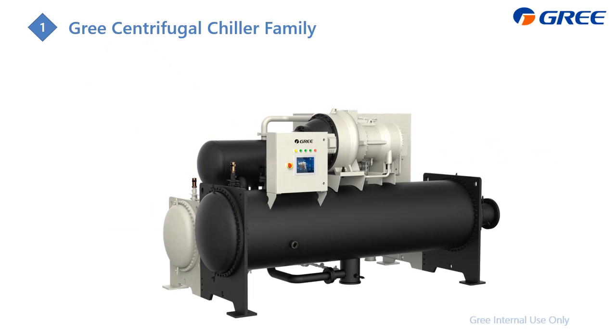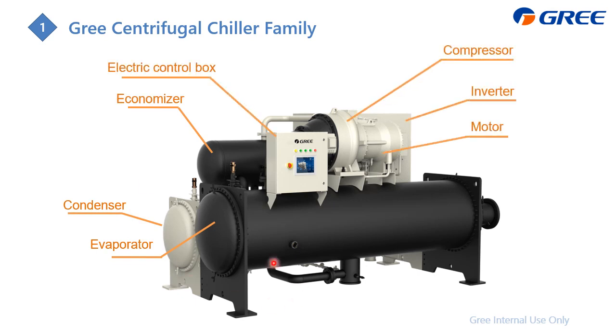This is the front view of the Gree centrifugal chiller. Let's recognize the components first. And this one, the black one, the black cylinder, you can also find it. It is the evaporator because it is doing cooling, so the surface always has insulation. And this one, condenser. No need to put insulation on the condenser, just leave it, it's okay. And this is the economizer. This can raise the system efficiency. And this one is the electrical box. It's for the power supply. And this one is the compressor, the most important component inside.